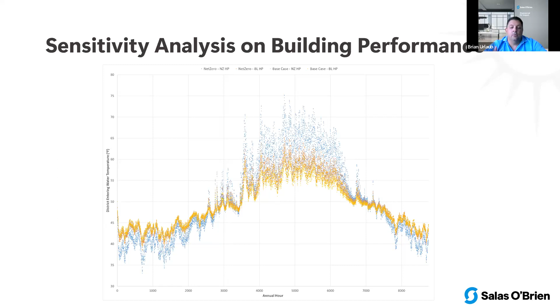And then, of course, we ran our TRNSYS model, which is really key to these types of designs, because we need to model that ambient temperature loop and know the temperature between each building and each injection point of energy along the way, so we know one customer isn't being penalized for being in a certain location versus another within that ambient loop. Our goal on this project was to maintain a minimum of 5 degrees between any energy source.